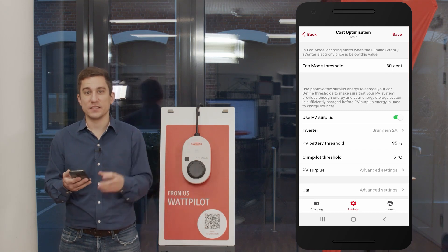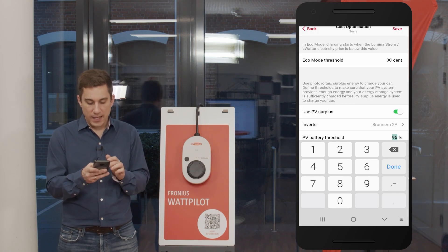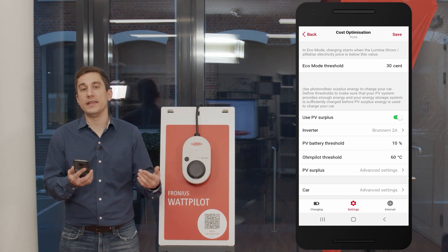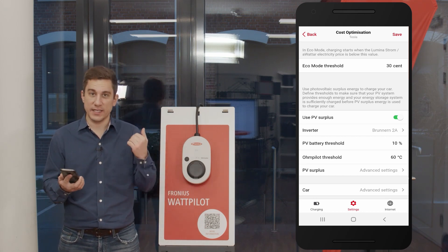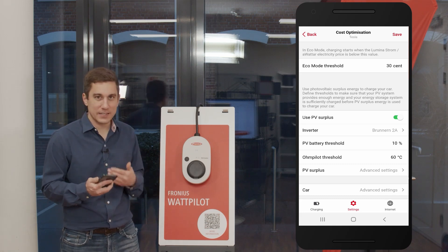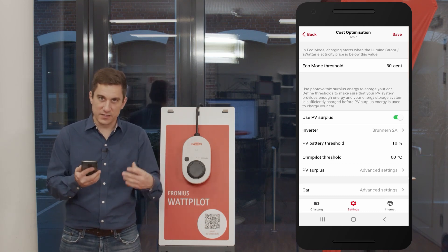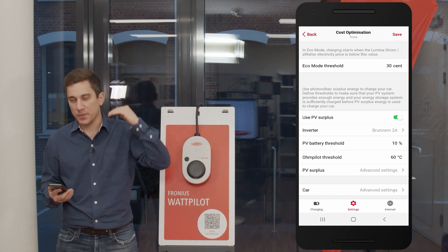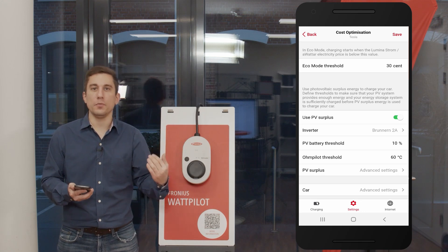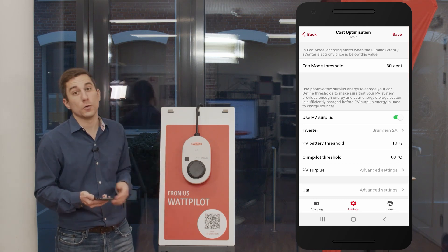In the third example, we want to prioritize the Fronius Ohmpilot, so we set a relatively high temperature — for example 60 degrees Celsius — and set the PV battery threshold down to 10% state of charge. This means the Ohmpilot will be operated until the hot water reaches 60°C. Once the battery SoC is at 10% and the hot water is at 60°C, the Wattpilot will receive the energy. Additionally, in the inverter web interface, you set Ohmpilot as priority one and the stationary PV battery as priority two.